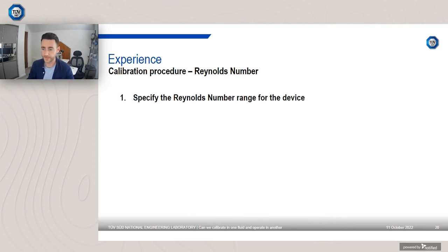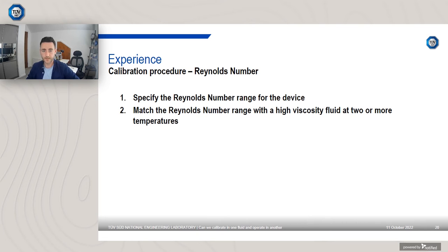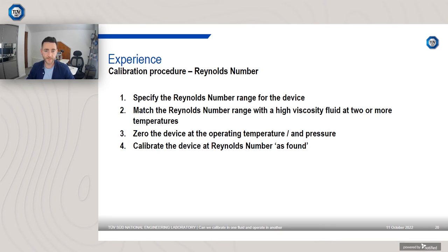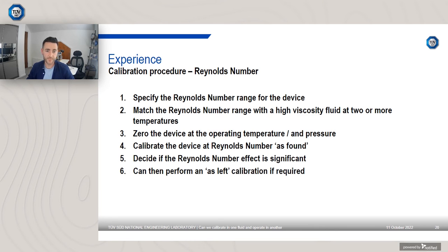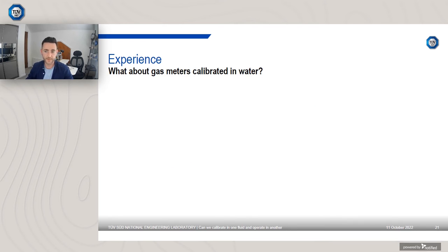So the calibration procedure would be this. We would specify the Reynolds number range for the device. You try and match that Reynolds number range with a high viscosity fluid or medium viscosity fluid at two or more temperatures. Just gives you a bit more confidence the more temperatures and viscosities that you have. Crucially, you want to zero the device at operating temperature and pressure. Then you calibrate that device at the Reynolds number as found. You decide if the Reynolds number effect is significant, and if it is, you can then potentially perform an as-left calibration to adjust for that, if it has to be, the results pulled up slightly or pulled down. In that case, you'd be adjusting the mass factor.